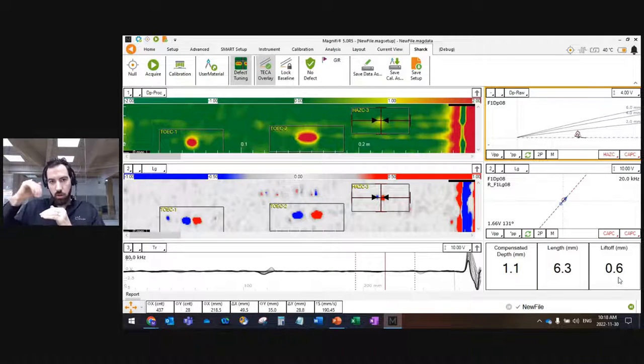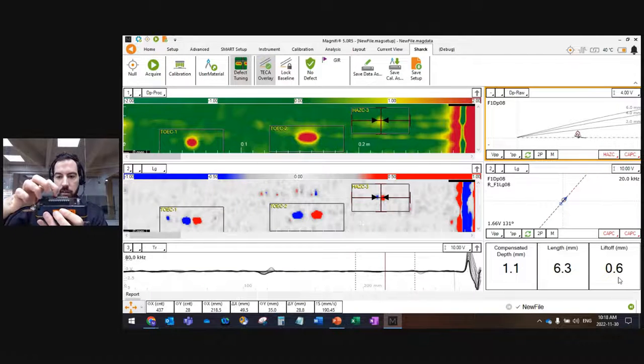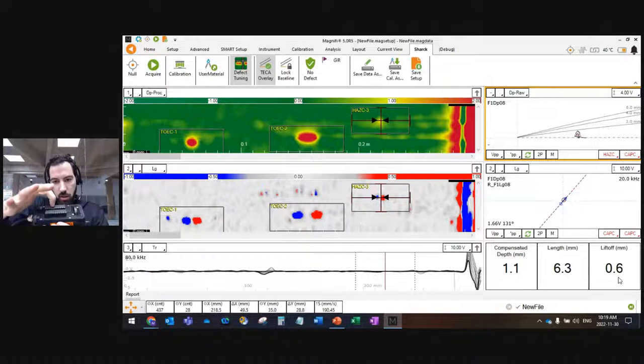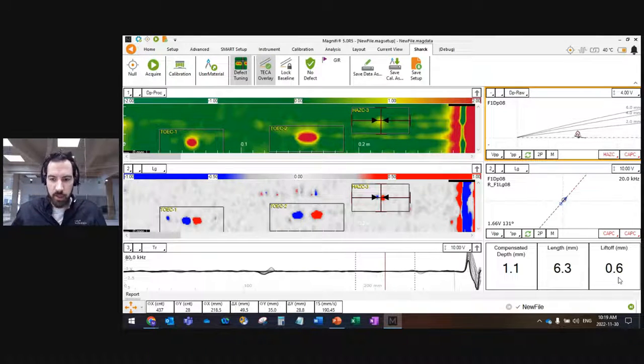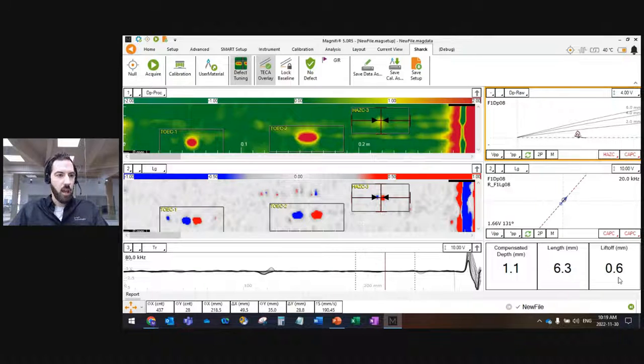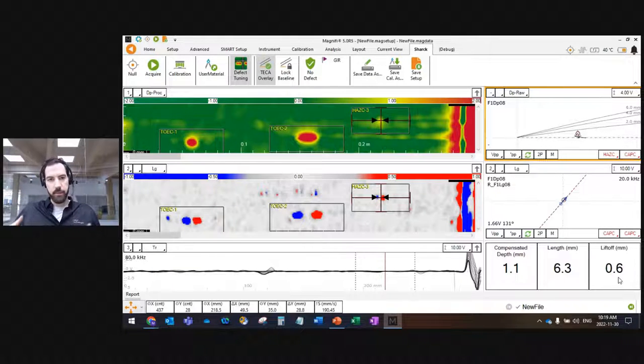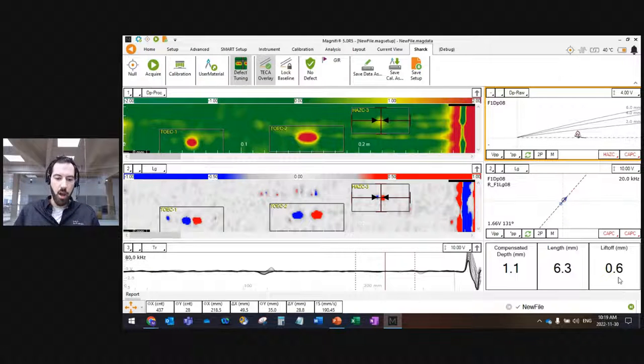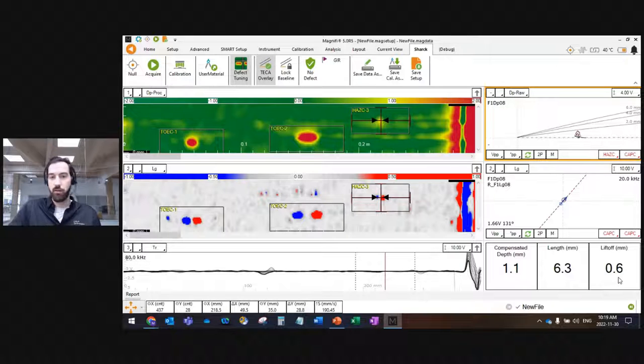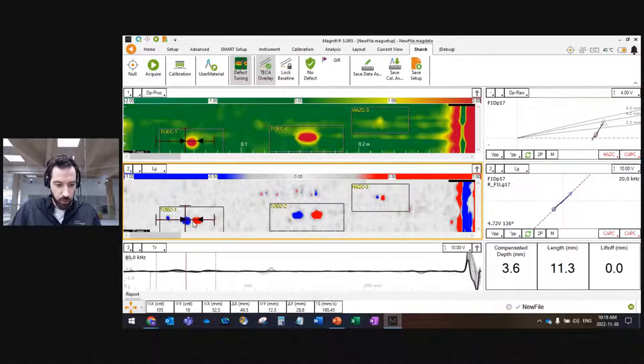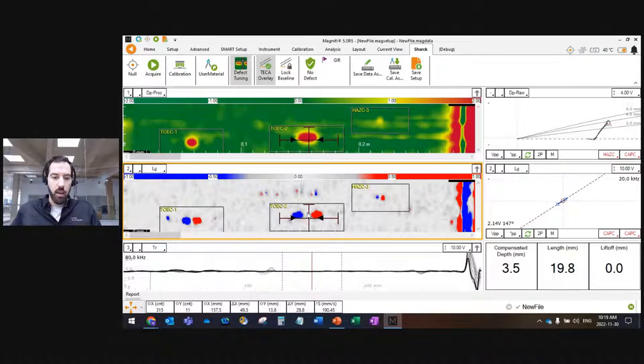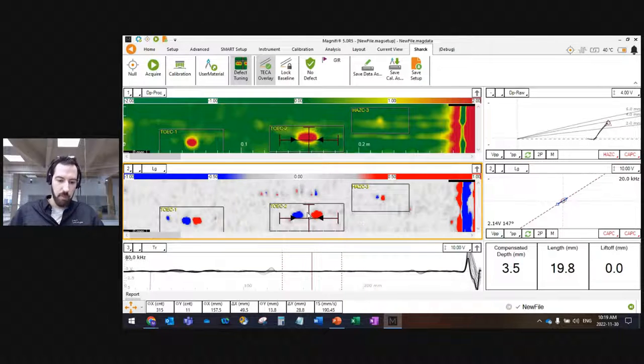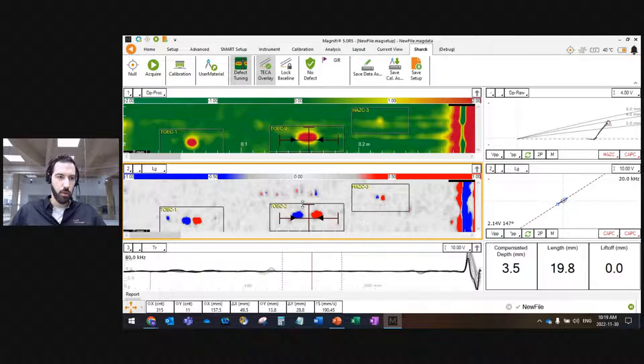If there's some geometrical features, my weld here is not too rough, it's pretty good. Sometimes in the field, you have all these really bad welds that are from the 1940s sometimes, they're just not in good shape. It will create a little bit more noise in the data. But it's very easy to differentiate what is a crack from what is just a bump, thanks to this blue and red combination. If you have the opposite, if you have red, blue, or if you have nothing at all, it means it's not a crack. It's something else. It could be a bump, it could be a weld splatter, it could be a hard spot or something like that. Just knowing what you're looking for is very useful when you use both C-scans.